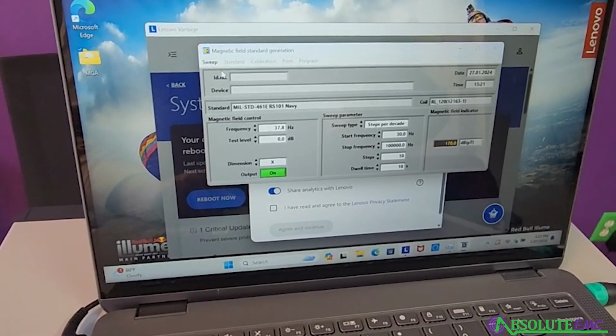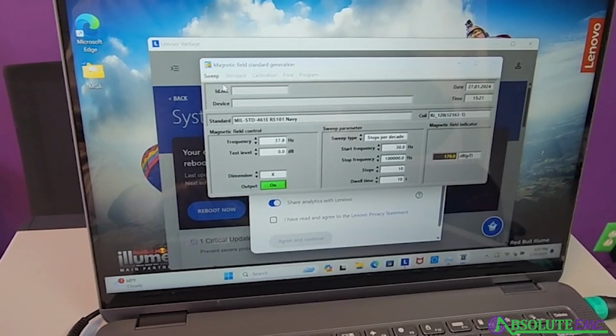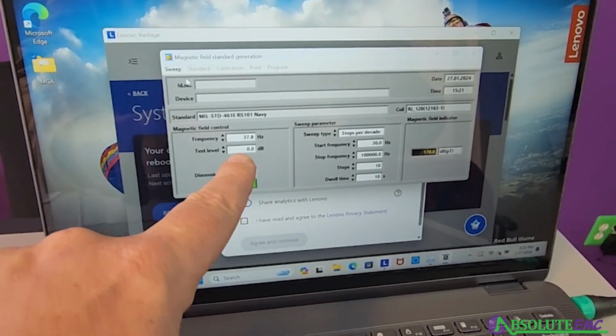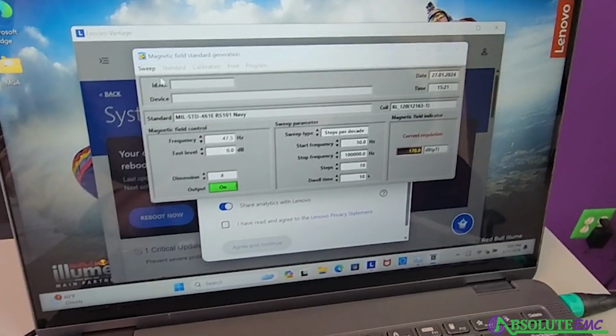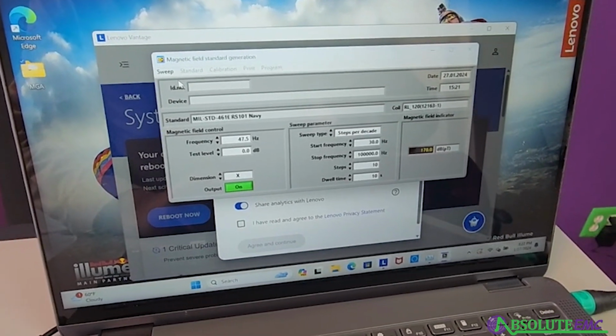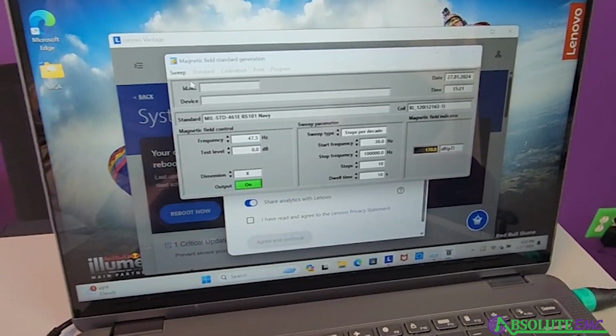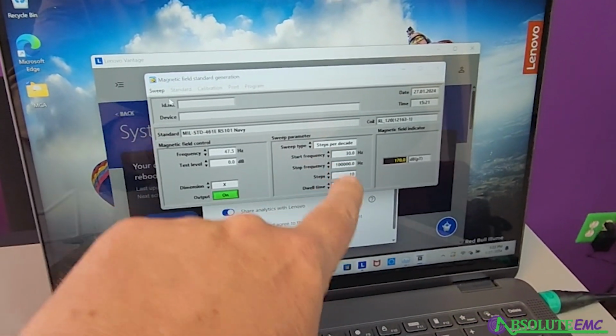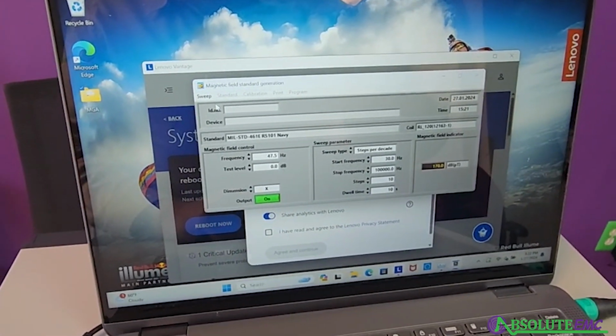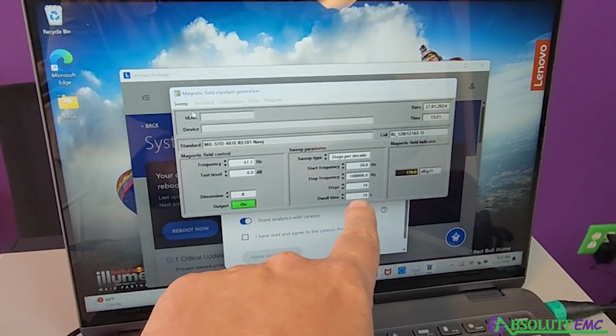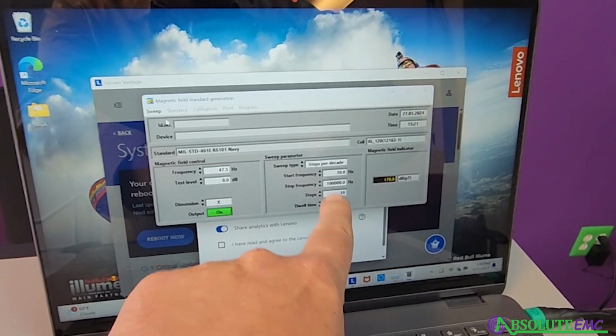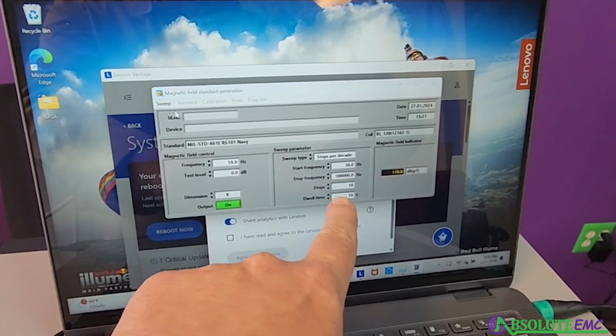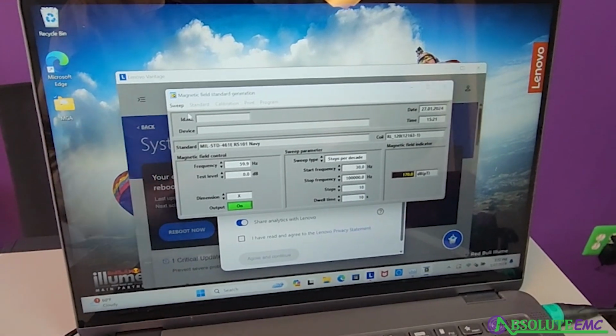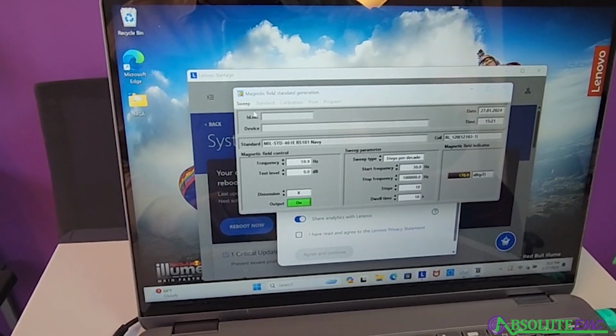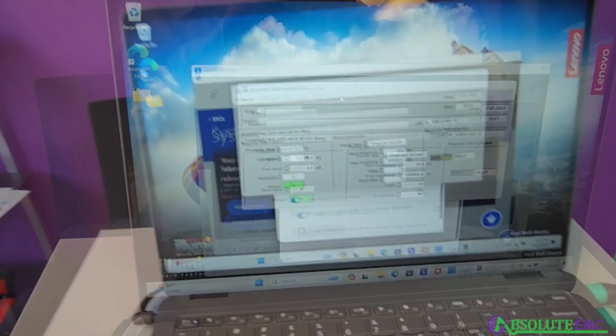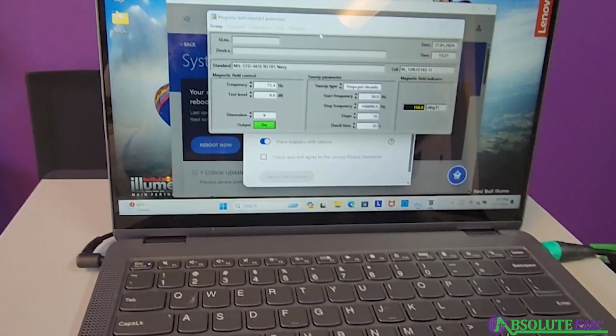it's measuring. We can, before we run the test, also make some modifications by upping the test level. Say we want to do some margin above or some margin below. We can change what axis we're testing. We can narrow the start and stop frequency range, and we can change our step sizes. Right now we're at 10 steps per decade, and we can change our dwell times. We're doing 10 seconds per frequency. And some more things we can go over here.